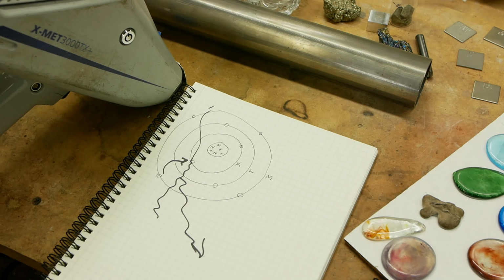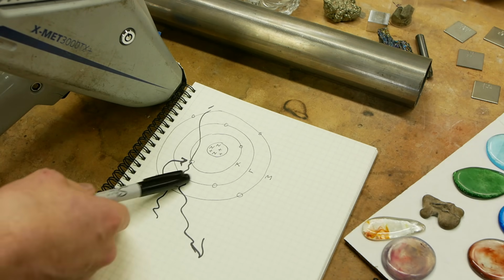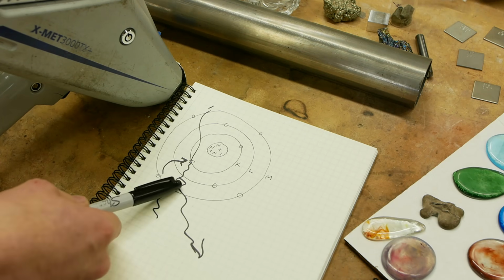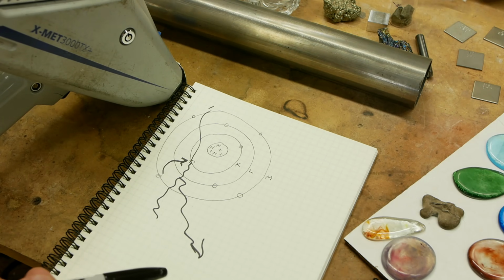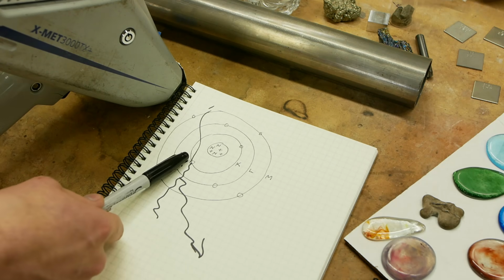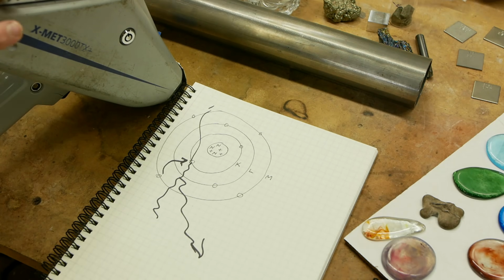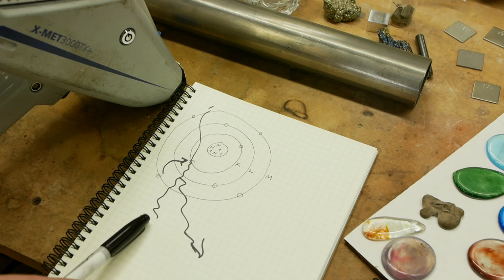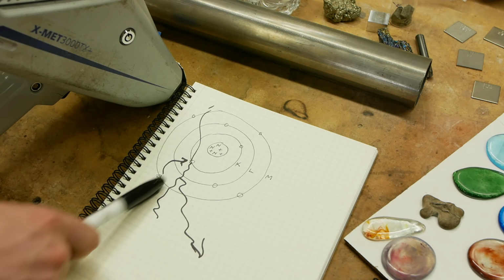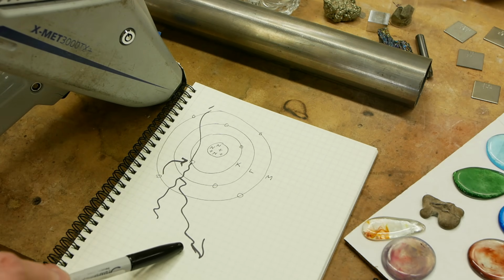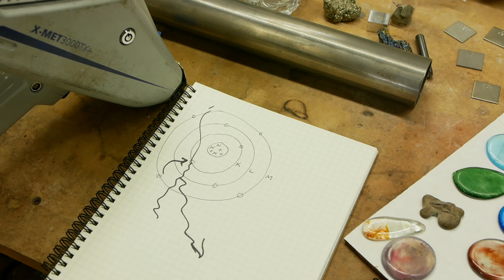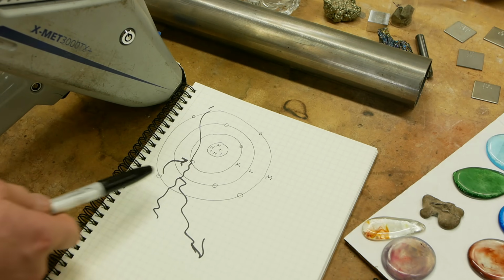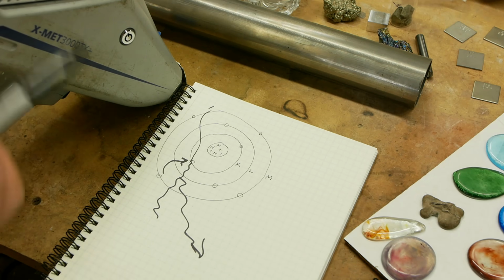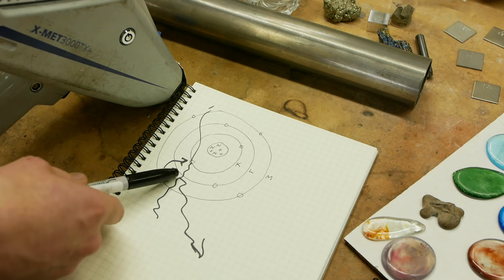You can see that there's actually another limitation here. If the returning energy is so low that it is absorbed by everything that's between our detector and the thing that's emitting it, then we can't effectively detect it. And this ends up being a really big practical problem. So if we're inputting energy at 40 kilovolts, right, because I said that the X-ray tube in here operates at 40 kilovolts, so let's just say it's a 40 kilo electron volt photon going in. If our return is only 500 electron volts, let's say, it's a very, very weak X-ray. It's possible that even the air and the construction materials of the detector itself would absorb that photon.